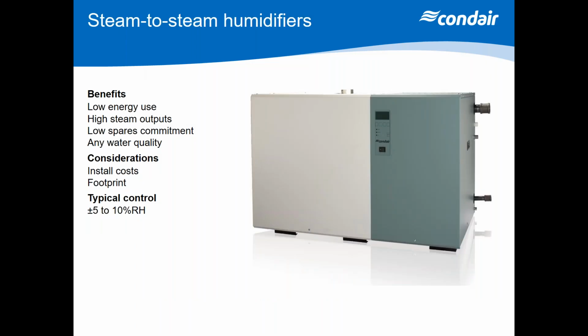There are some other types of humidifiers out there. There are steam-to-steam units, and this is really something that you see in pharmaceutical applications, and it's basically a big heat exchanger. So you get live steam coming into one side of it, and a clean water supply going to the other, and we produce steam at atmospheric pressure. Low energy use because we've already got the steam going around the plant, and high steam outputs, up to 200-300 kilos an hour. Install costs and footprint are very similar to the gas units. Of course, you don't have to consider any fluing. And plus or minus 5 to 10% RH control. Again, it's just a big heat exchanger.